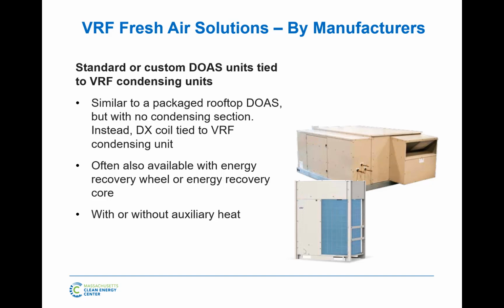So this condensing unit now can handle the heating and cooling, or what we call the trimming. Trimming is, I got a wheel, so on design day I'm coming out at 50 degrees. I want a coil to take it from 50 to 70. Or in the summer, I've got a wheel, so I'm taking my outside air from 95 degrees down to the high 70s. Now I'm going to put a coil to cool it to 55 and reheat it so I can do all my dehumidification. Those are all fresh air concepts that you can do depending on your application.